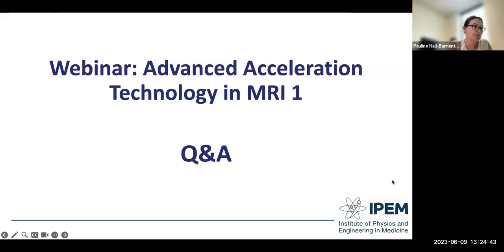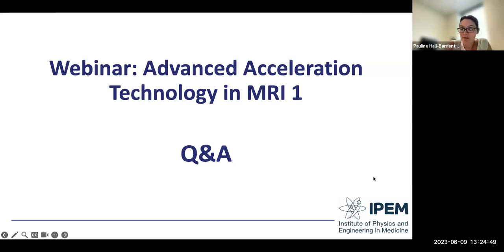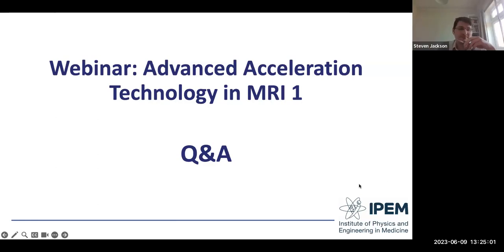The utility of combining SMS with DeepResolve Boost would be particularly valuable for patients you might only get two or three minutes out of, or who are particularly uncomfortable. It's certainly possible. 19 seconds would be particularly useful for paediatric imaging. An implementation question from Owen: how have people managed having variable booking slot lengths for different exams across a fleet of MR systems — some with AAT and some without? Not easily. It requires a lot of communication with the booking team, updates to RIS, and it gets difficult when trusts cover more than one hospital.